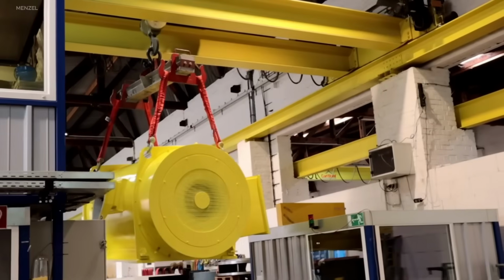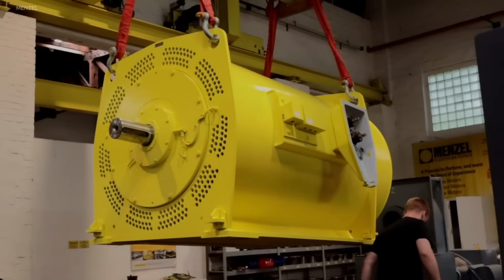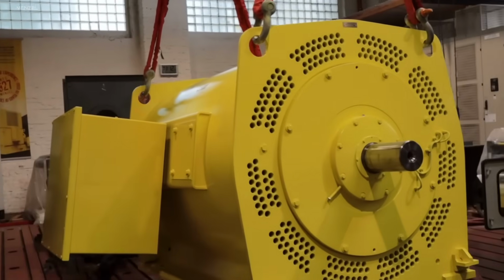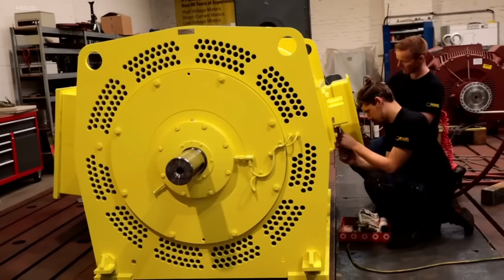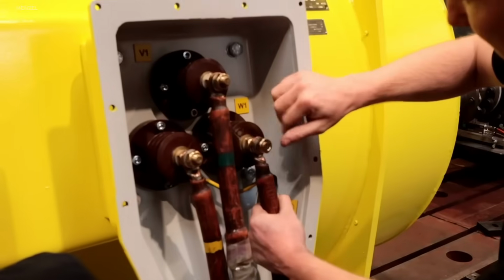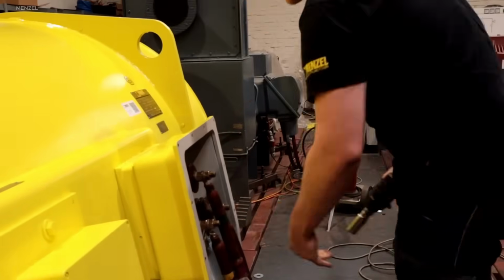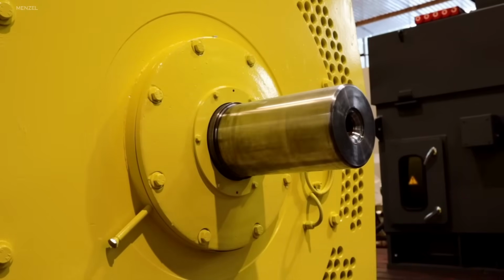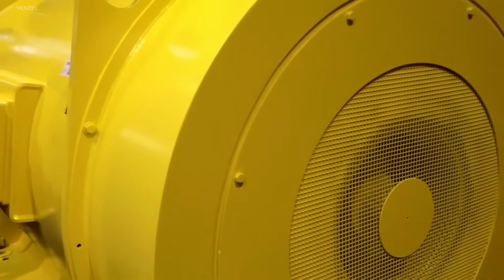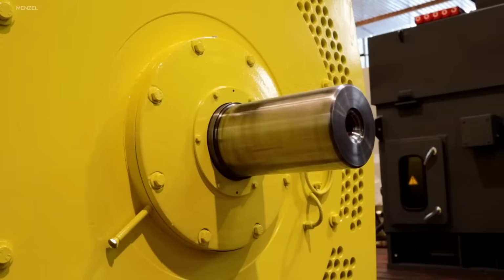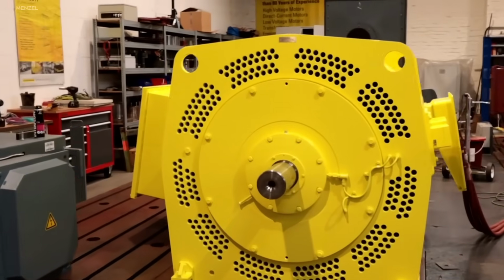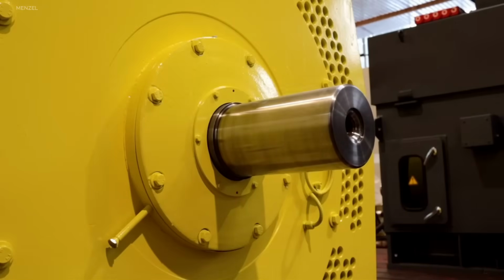Cables are connected to the 1.7 megawatts electric motor, and engineers inspect all components to ensure proper setup. Mounted in foot design IMB3, the motor is explosion-proof and air-cooled via a tube jacket heat exchanger. After confirming alignment, power is supplied gradually using a 6 kilovolts inverter on the test bench. The squirrel cage rotor begins turning, reaching 1,486 revolutions per minute under close monitoring. Internal fans circulate air to maintain temperature, while external fans dissipate heat. Performance and vibration data are collected throughout the startup phase to confirm system integrity before operational deployment.